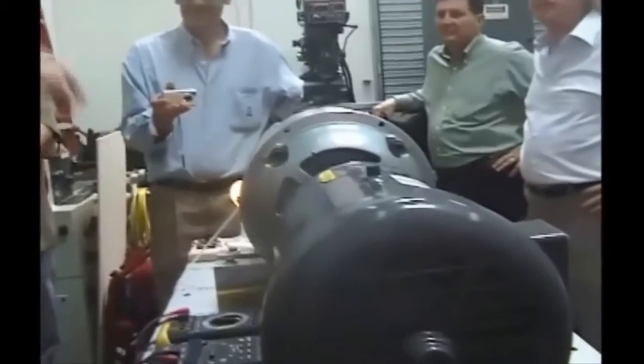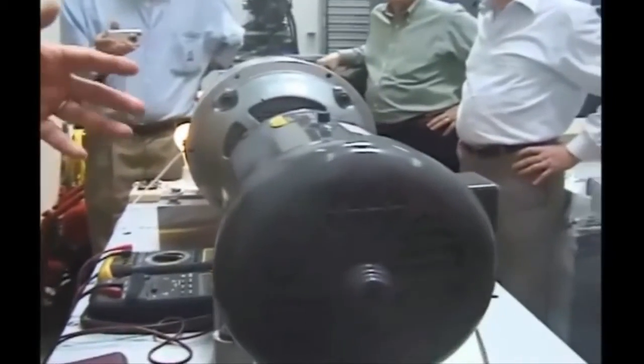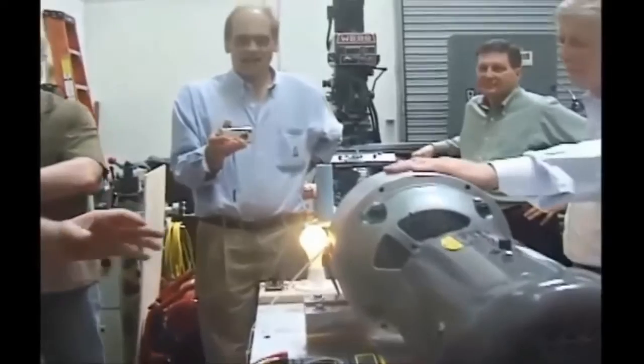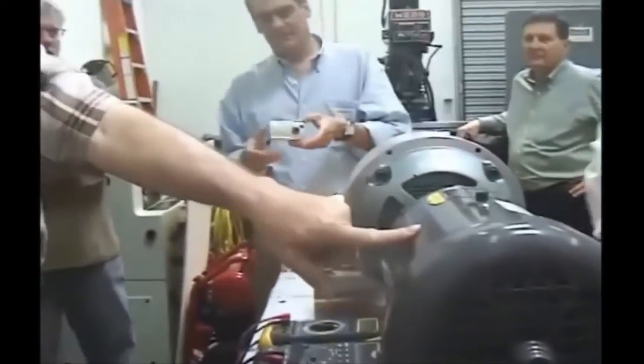So what we would do normally, the minute that speed starts to pick up, the power in this has to be lowered. Automatic regulator. And then what would happen, of course, is that ultimately you get this force right. All that the prime mover has to do is cover the frictional loss.